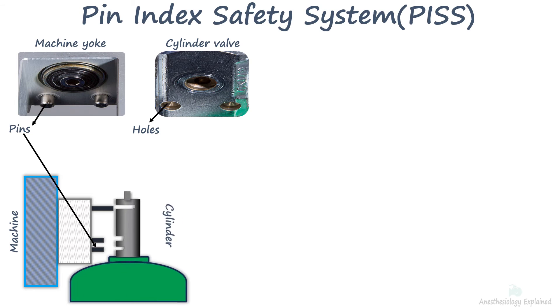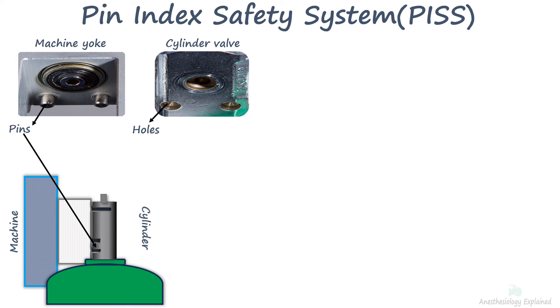The pin index safety system, or PISS for short, is a mechanism used for attaching cylinders to regulators and anesthesia machines. It involves two precise holes in the cylinder valves that perfectly align with two pins on the receiving yoke. When these pins and holes don't align, the cylinder's port won't fit snugly into the nipple of the hanger yoke. This system was devised to prevent the inadvertent placement of a cylinder containing the wrong medical gas onto the hanger yoke of an anesthesia machine designed for a different gas.